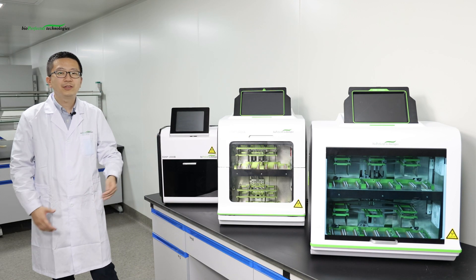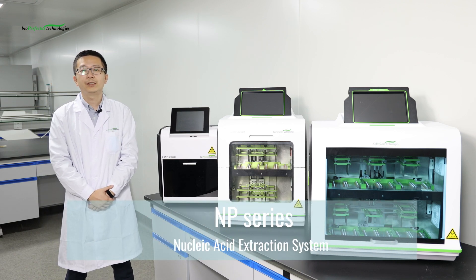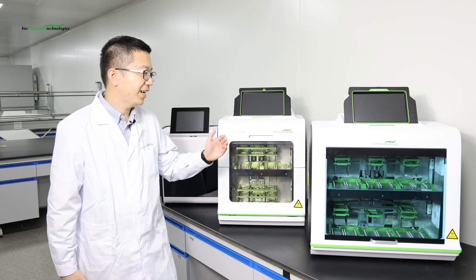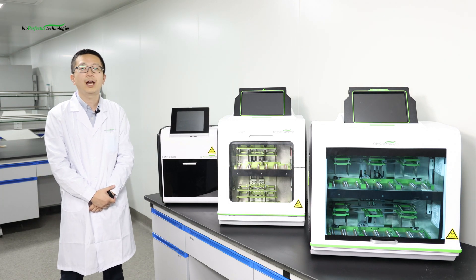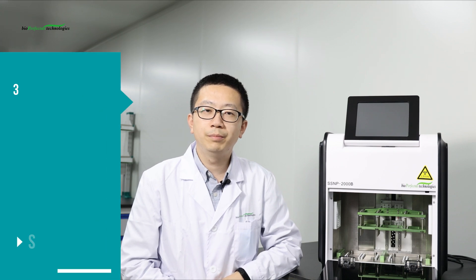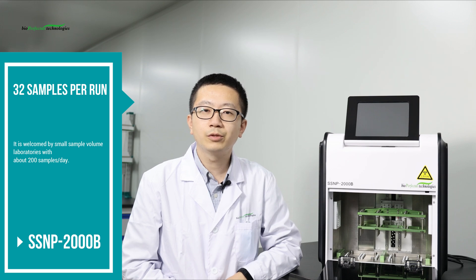On my left hand, what you can see is Bioperfectus SSNP series automatic Nucleic Acid Extractors: 2000B, 3000A, and 9600A. These three instruments apply the same magnetic bead method with different throughputs, providing flexible solutions for labs with different sample volume demands. The SSNP 2000B supports up to 32 channels per run — a smart and small instrument welcomed by small sample volume laboratories processing about 200 samples per day.